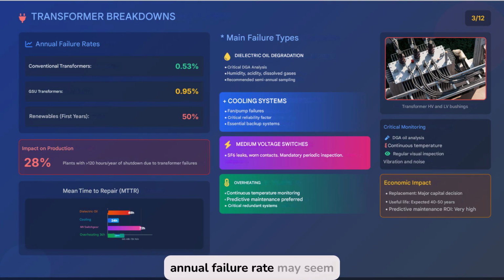Although its annual failure rate may seem low, when a breakdown occurs, the economic and operational impact is significant. It's the component that typically generates the longest and most costly downtimes, justifying priority technical and financial attention. Under normal conditions, conventional transformers have a failure rate of 0.53%, GSUs reach 0.95%, and in new photovoltaic plants, it can reach up to 50% in the first few years. This is due to factors such as lack of operating experience, adverse environmental conditions, and non-optimized technical configurations.